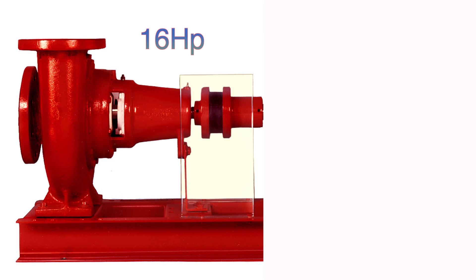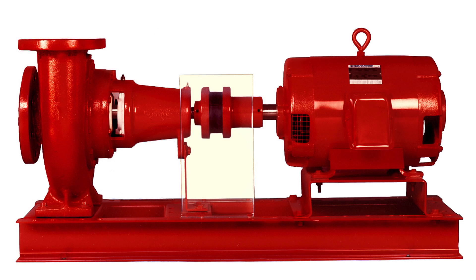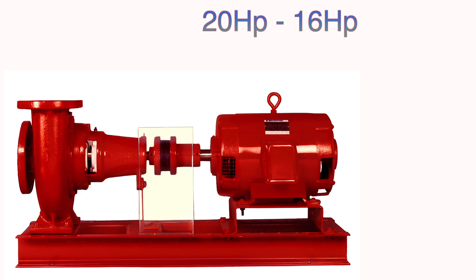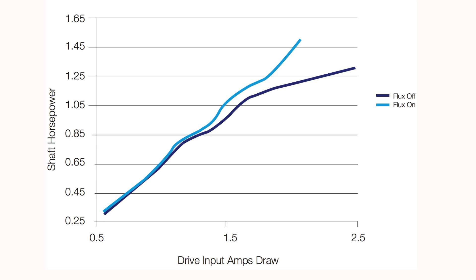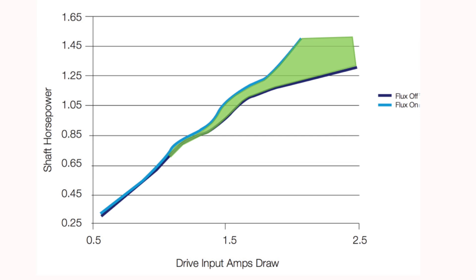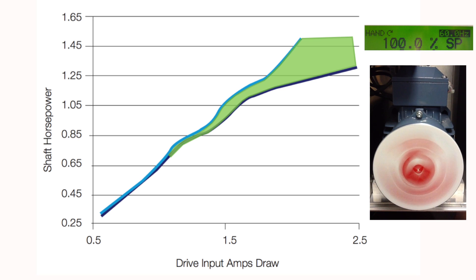Generally, you see a 20 horsepower motor put on a pump. Now assuming that your application is fully torqued and using all 16 brake horsepower, there's still 4 horsepower left that is being unutilized. Flux optimization removes that unused, wasted energy from the motor, even if that motor is running at full speed or at 60Hz.